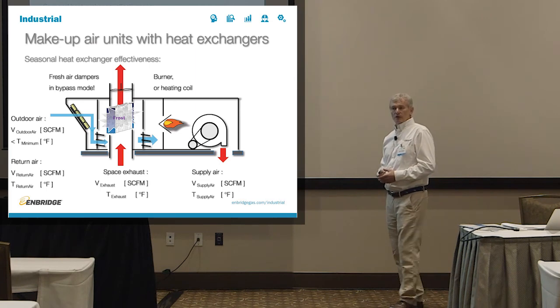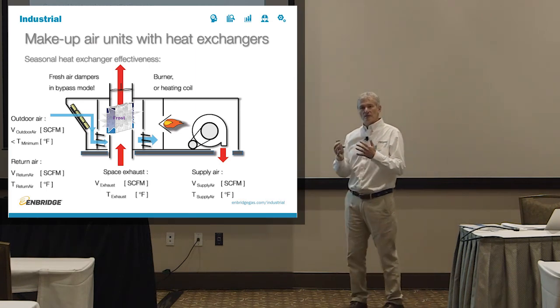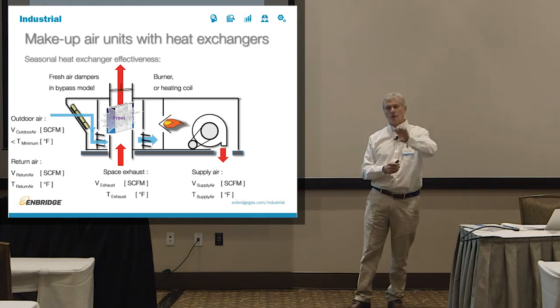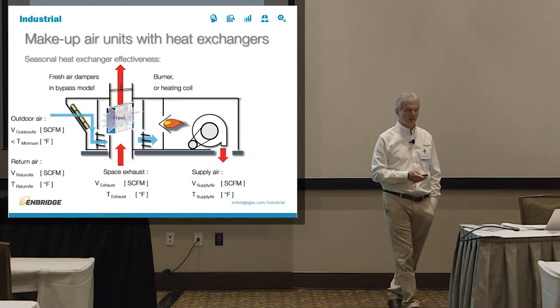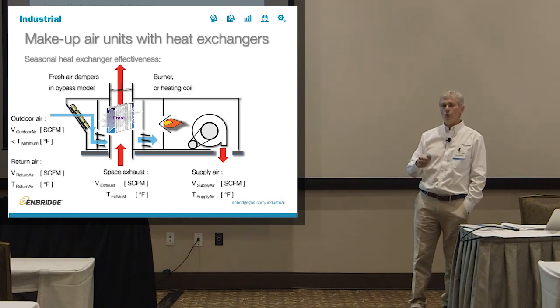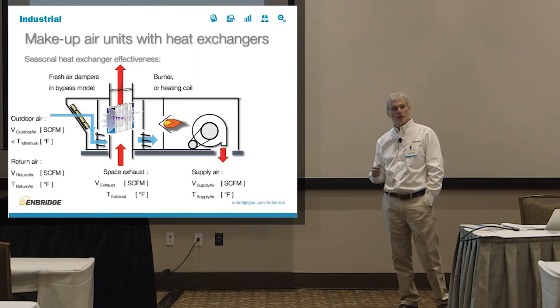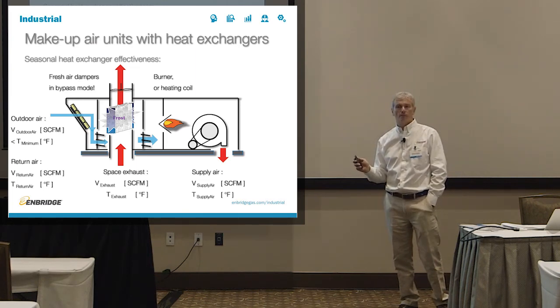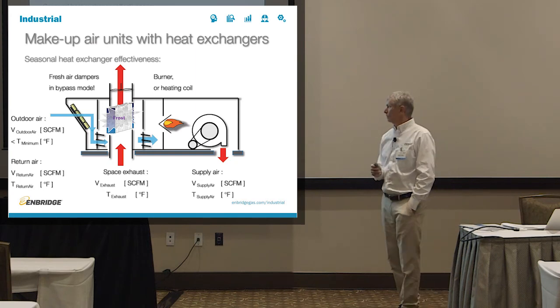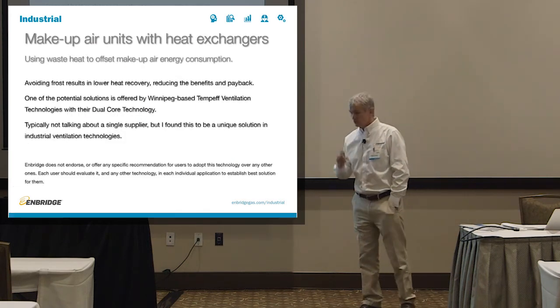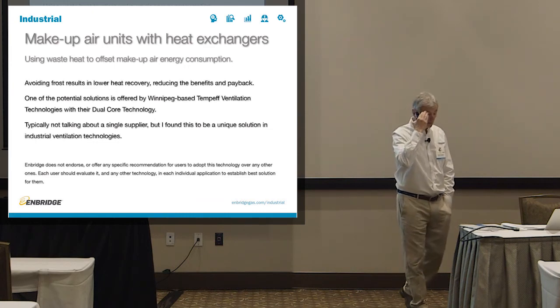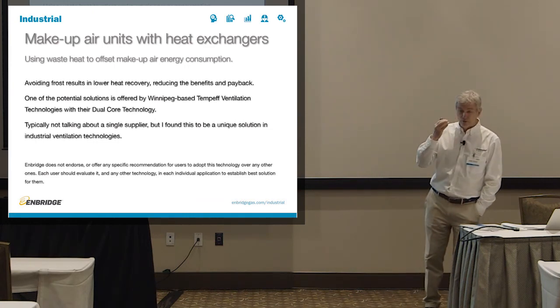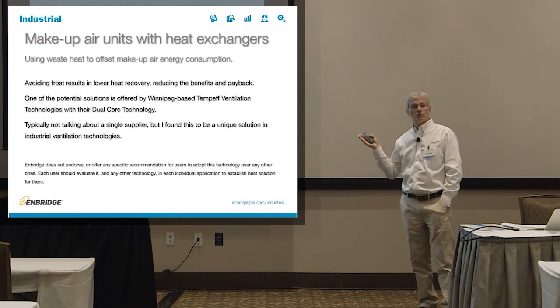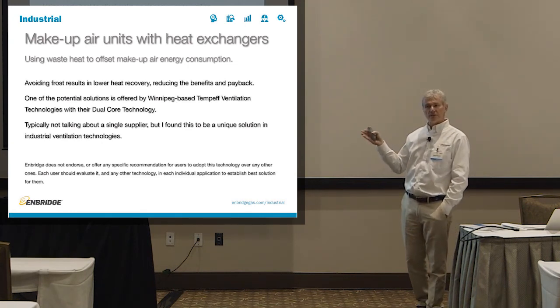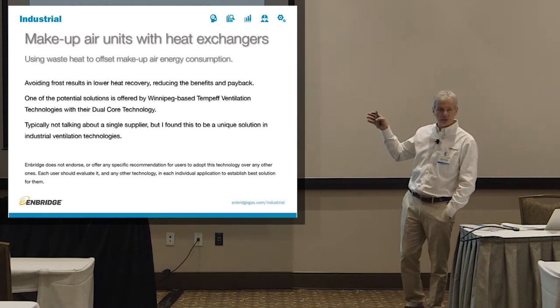Return air plays a role here, because if you have some return air, you may help with that frost. They may use that return air to essentially defrost the heat exchanger at times. Again, know exactly what you're getting. Don't just settle for, oh, I have a heat exchanger and it's going to recover my heat all year long. So usually that was a showstopper for me when I evaluated makeup air heat exchanger systems, because the cost and the benefit, when you take into account this heat exchanger effectiveness over the entire season, just didn't pay out.